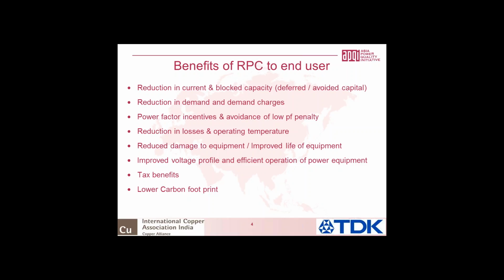You have an improved voltage profile. For example, I know a couple of utilities where they went for a statewide installation of reactive power compensation systems, not so much to reduce the T&D losses, but to improve the voltage profile. India still has a classical low voltage problem where in some parts of the country, even today after 6 or 7 o'clock, the tube lights don't come on because they don't even have the striking voltage. Voltages could be as low as 160 volts, which you can witness even today. So by adding these shunt capacitors, the voltages even at the remote feeders can be boosted up, which means even a simple piece of equipment like a tube light would operate properly.